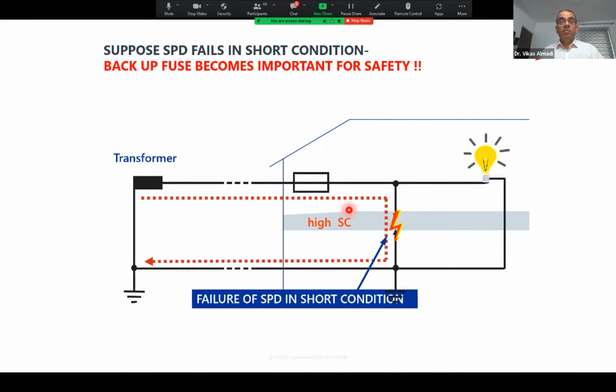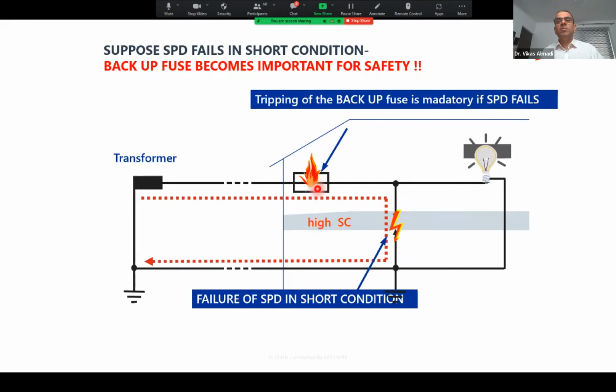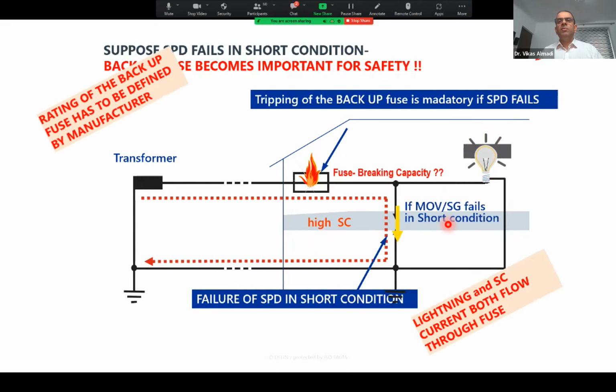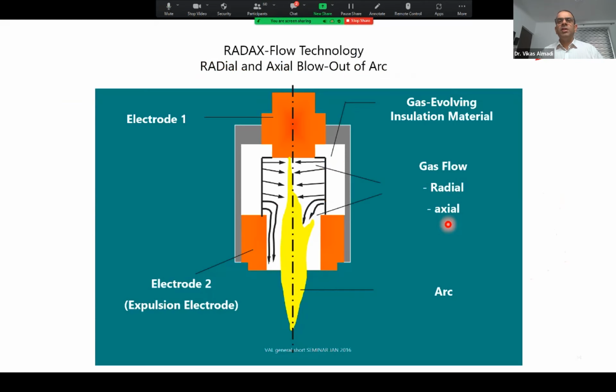Now, if this kind of scenario happens, there is a possibility of failure of the MCB or fuse, or tripping of the fuse. This is not failure, but tripping of the fuse, which can still cause a discontinuation in the services. So this is also not desired. For that, it is important to choose the fuses nicely. That is number one, and choose the SPD also nicely, which not only discharges the lightning current, but also limits the short circuit current. Limiting of the short circuit current is very, very important apart from the lightning discharge or surge discharge.